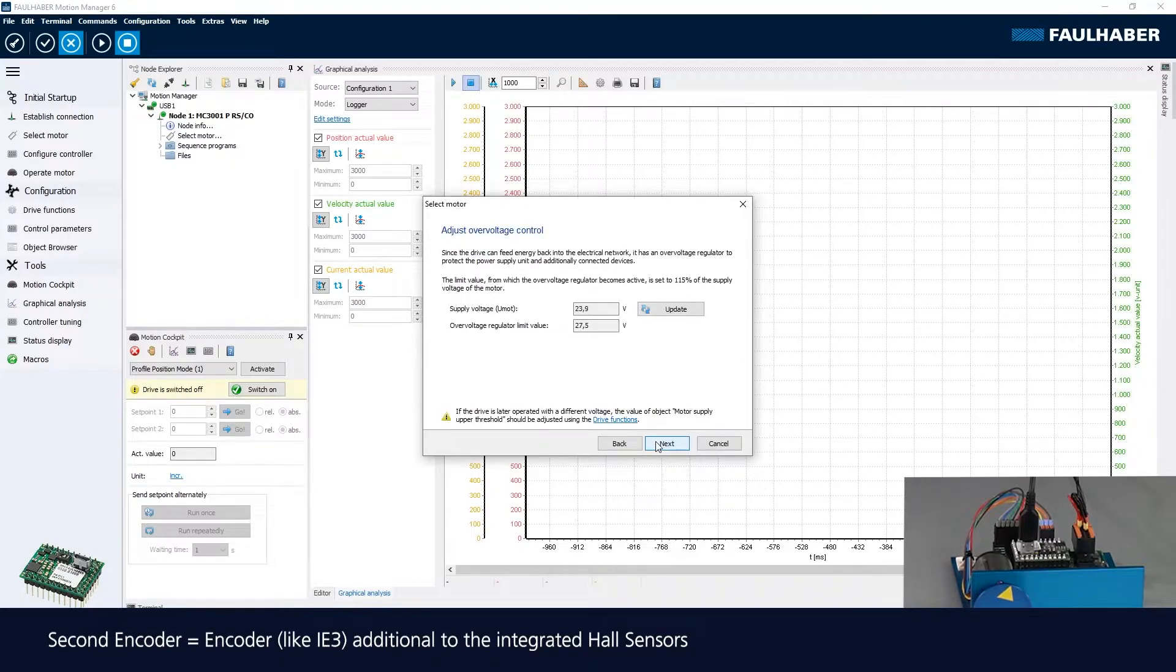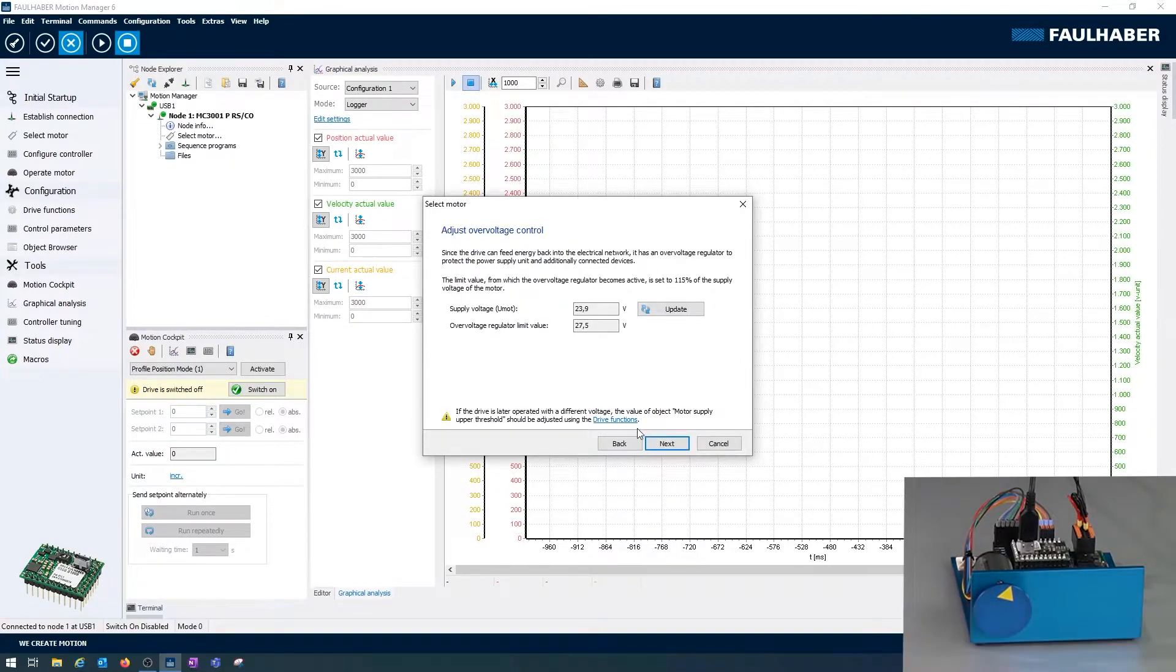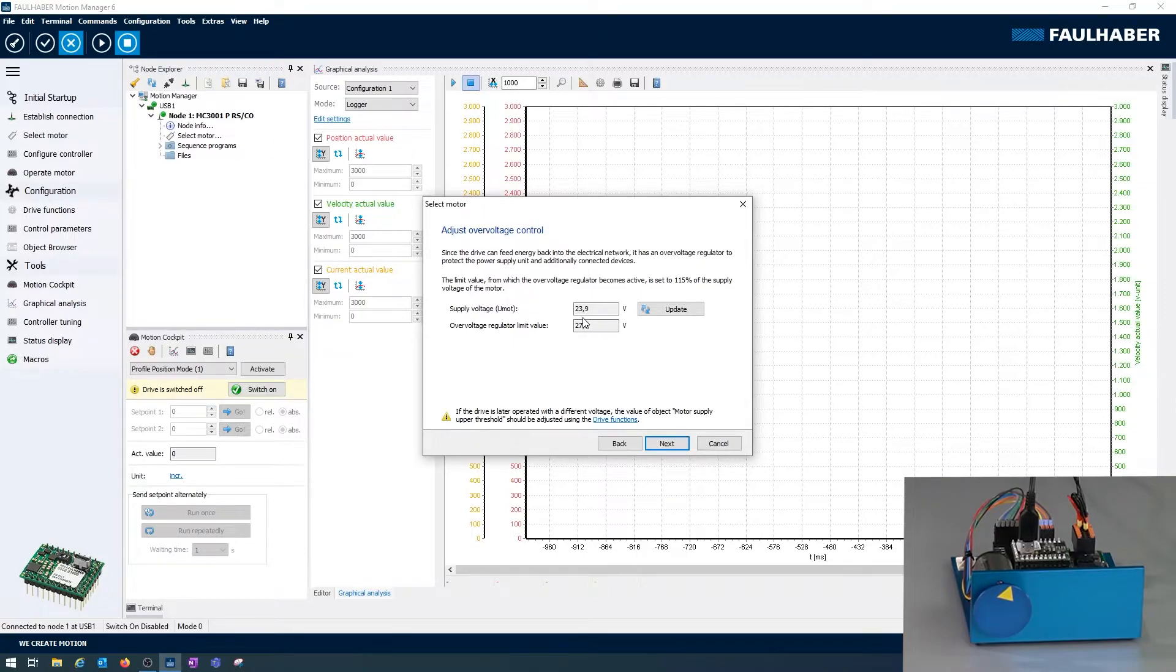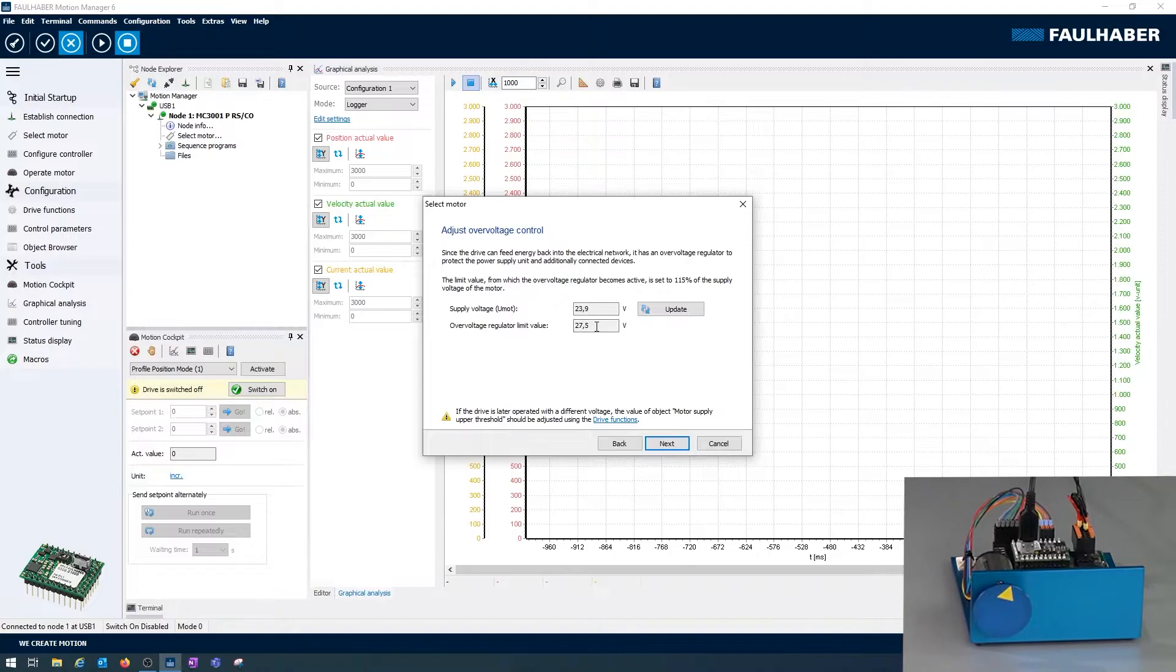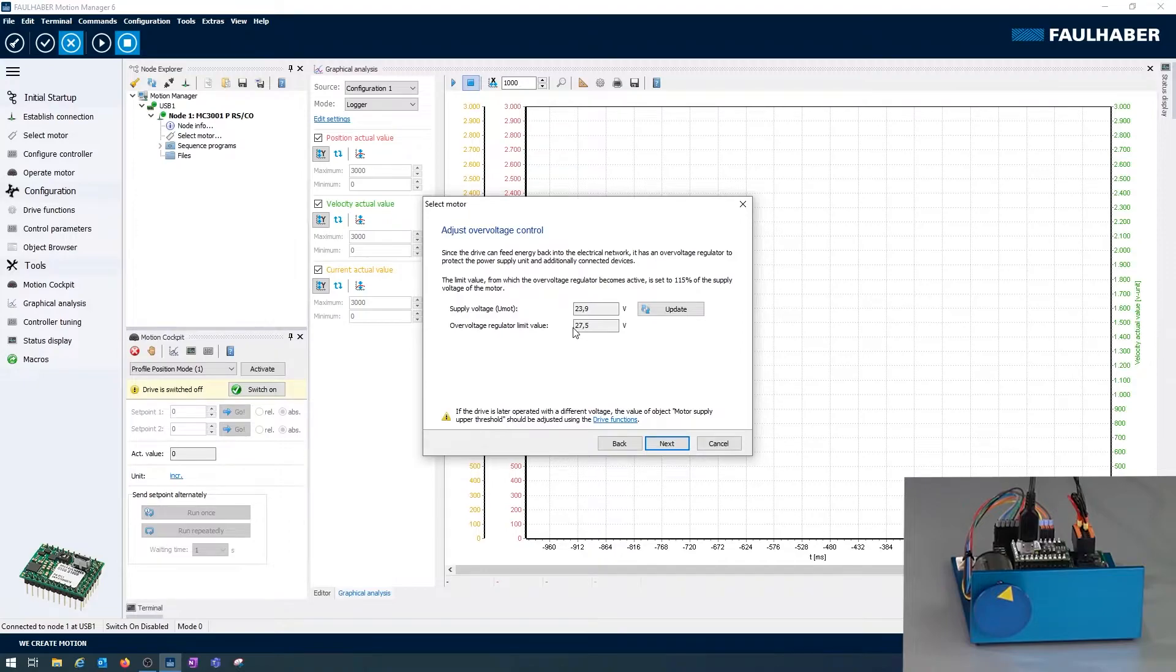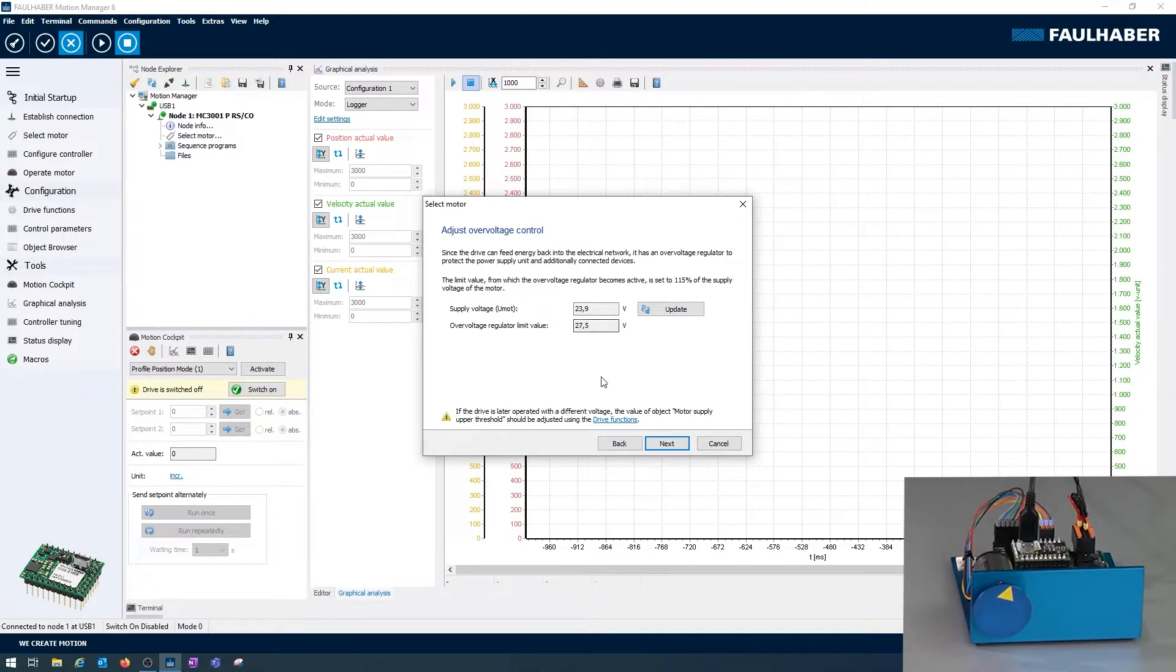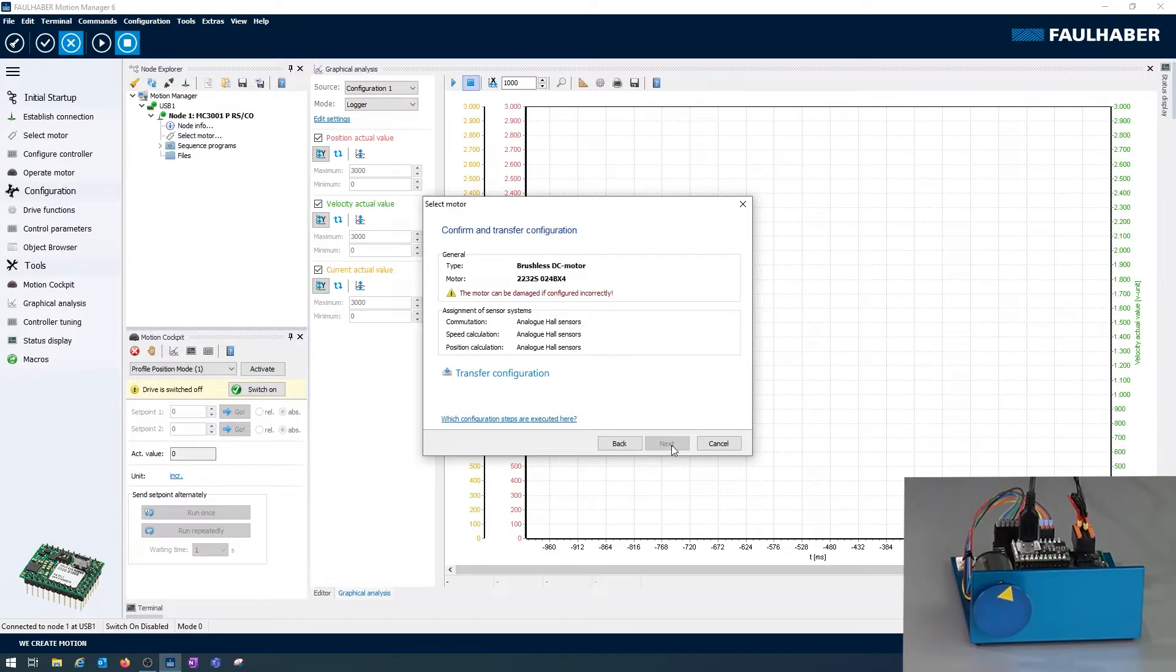Next is about the power range. I mentioned the power good LED and here is the range that's configured by default. The actual supply voltage is measured and plus 15% is set as the maximum value allowed for a power good range. If the power exceeds that range it might even shut down to prevent any damages from connected electronics. And now we're done here.